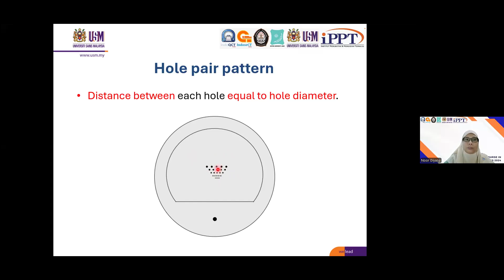This is one example of phantoms. Next, we can also use a phantom with different holes, which have equal distance and equal diameter. So we can count the distance between each hole. In CT, the limiting resolution is usually 0.5 to 2 line pairs per mm. As compared to screen film, which actually has more resolution, 4 to 20 line pairs per mm. But nowadays the limiting resolution is increasing due to advancement in technology.